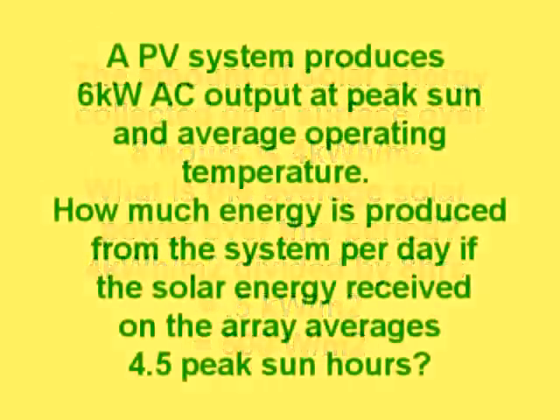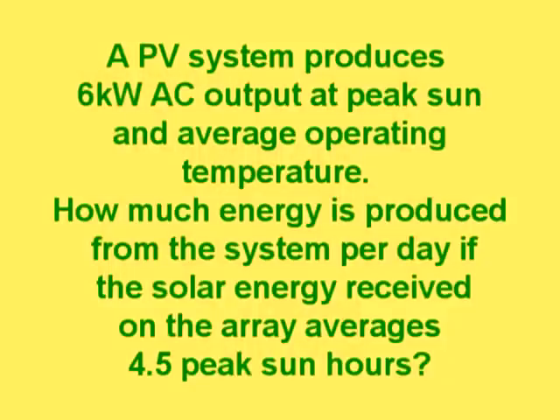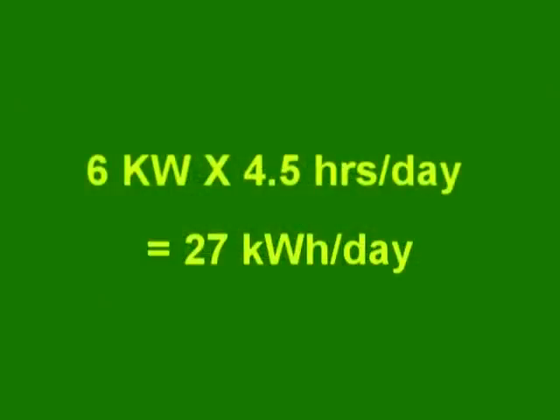A PV system produces 6 kilowatts AC output at peak sun and average operating temperature. How much energy is produced from the system per day if the solar energy received on the array averages 4.5 peak sun hours? 6 kilowatts times 4.5 hours per day equals 27 kilowatt hours per day.